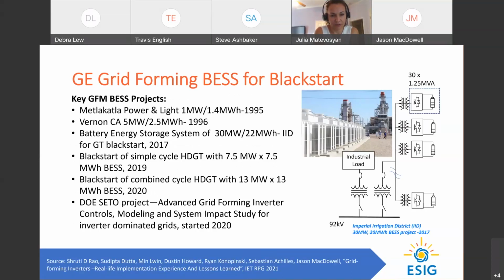GE has a number of projects using grid forming battery storage in various applications. The oldest being a community in Alaska, where the battery powers a microgrid for the community. It's a relatively small project, but probably one of the first for microgrid application, implemented relatively early on. Then a project in California, where a 5 megawatt battery storage provides security of supply to an industrial load. At times it operates grid connected, and at times it powers up an island with that industrial load isolated using grid forming battery.